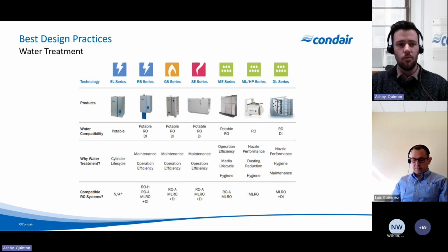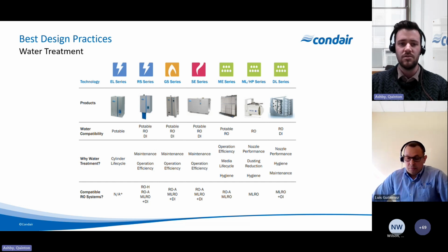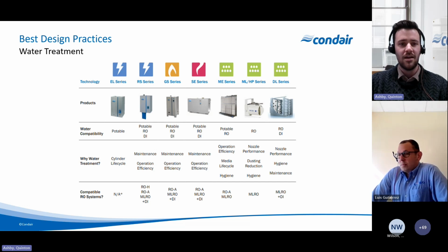So just kind of covering water treatment in general, we do have a water treatment guide available on our website, but as I said before, not all water is created equal. Certain units do have certain requirements for water. As you can see, the EL, which is a regular canister system, has to use potable water because it relies on minerals to actually conduct that electricity, compared to the RS, which can use any type of water. It doesn't matter, it's using resistive. On the same side, there are specific requirements for adiabatic, so we need RO or potable, depending on it.